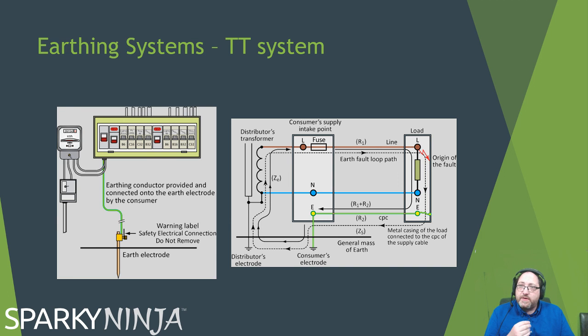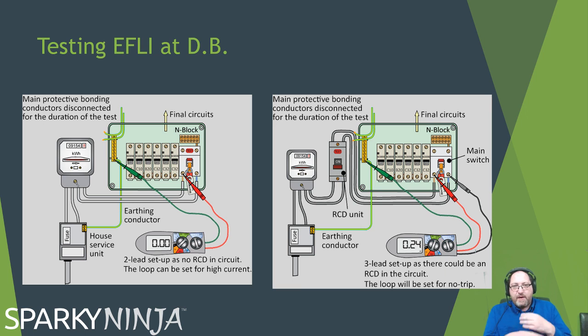With that in mind, you need to understand earth fault loop impedance and how the earth fault loop impedance path works. So with regards to measuring earth fault loop impedance at the board, it depends on if our instrument is 2 lead or 3 lead. If our instrument's 2 lead, we just go, as you can see there on the left, between line and earth. The important thing here is, if this is a ZE measurement, the parallels, you can see there the bonding has been disconnected, the main earth comes out and we go on the main earth, so we don't measure any earth that's brought in through parallel routes, through bonding, through water pipe work or anything. We only test the supply that the provider has given us.